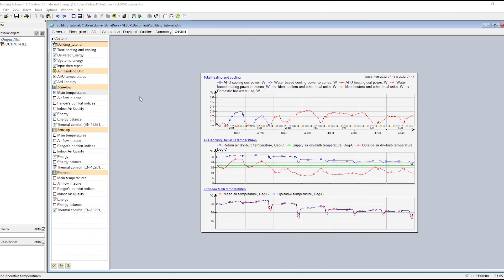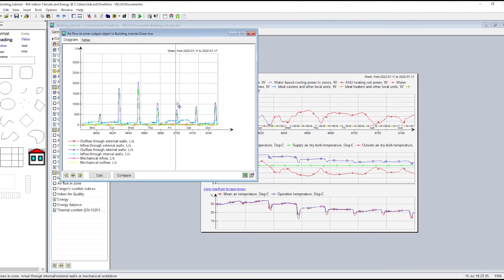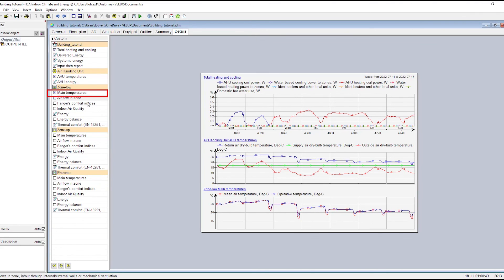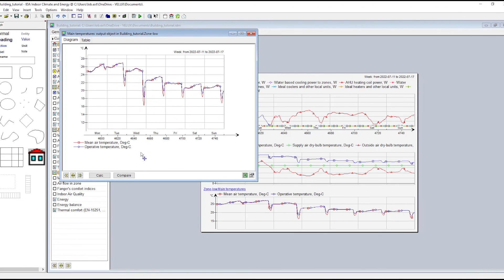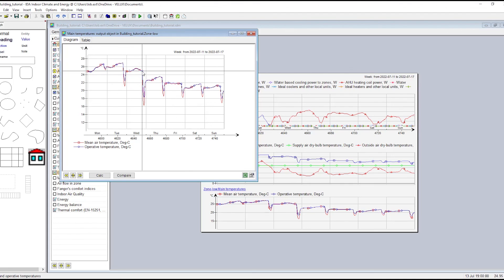After the simulation is completed, we can go to Details and investigate the results. The main focus is airflow in zone and the main temperatures, showing how much heat can be removed and how indoor climate conditions can be improved. Looking at airflow in zone for the week from July 11th to 17th, we can see the peaks of the airflow when the windows are open. According to the main temperature chart, this window opening strategy permits cooling the building significantly on warm nights. For example, on Wednesday, the indoor temperature dropped from around 25°C before the windows opened to 22°C the next morning. Thanks to a simple simulation, you can demonstrate the ability of your natural ventilation strategy to improve thermal comfort in summer.